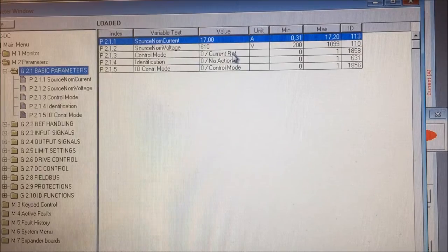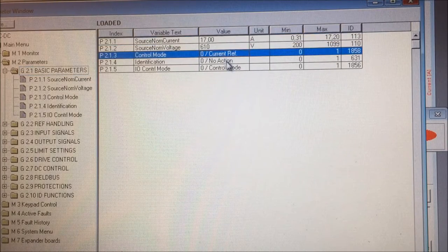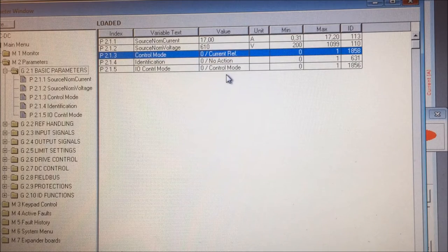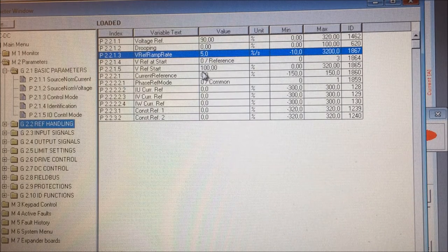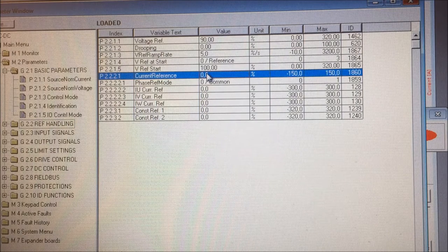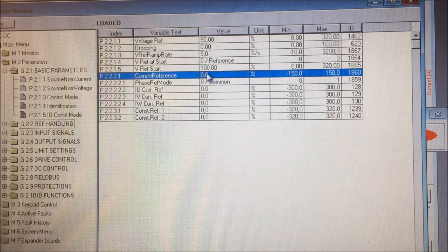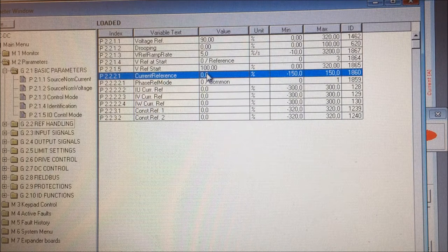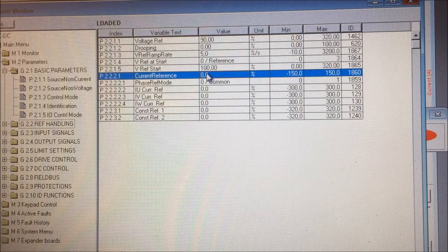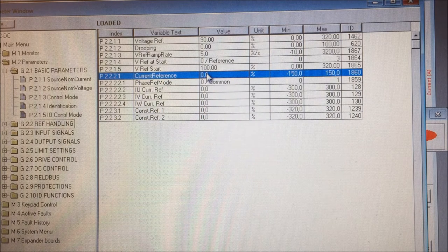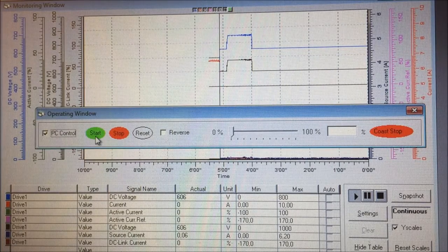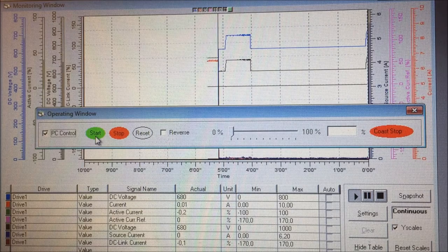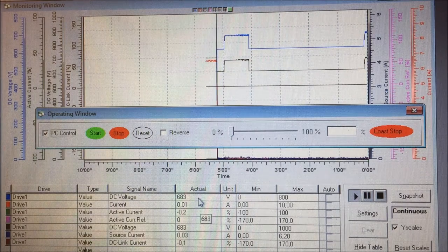The first time I start this DC converter, I want to start it in current reference mode. I will then go to the reference handling and I will tell it to go for 0 ampere. So it will start very gently. Actually, right now I haven't connected the active front end to my DC bus. I just want to see that it's able to produce 680 volts on its DC bus. Let's start the drive. It went to 682 volts.